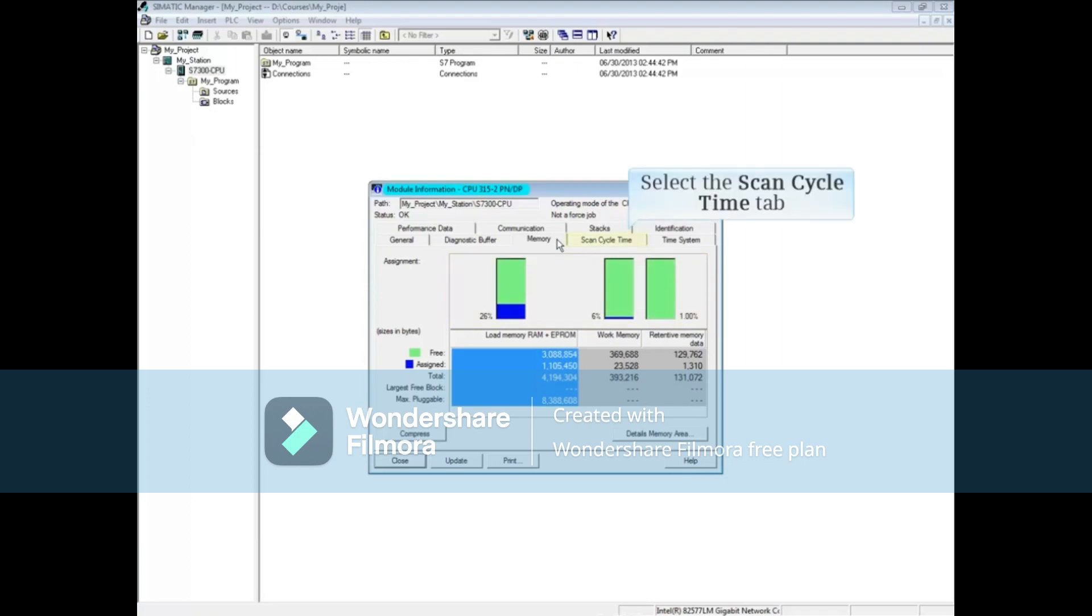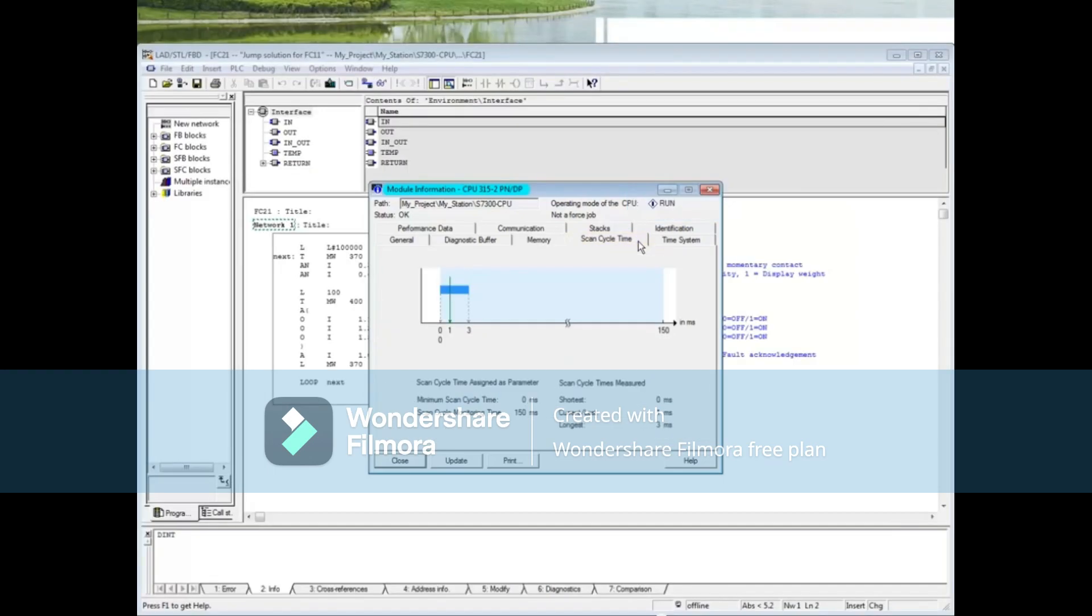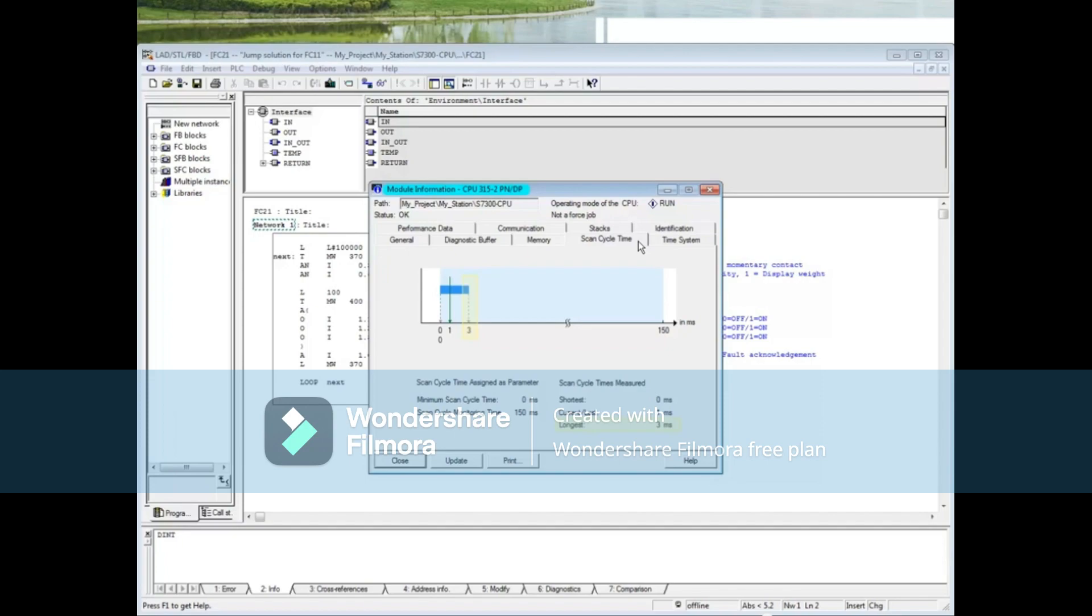Click on the Scan Cycle Time tab. This tab shows both graphically and in words the watchdog cycle time, which is 150 milliseconds, the longest scan cycle so far, which is 3 milliseconds, and the shortest scan cycle, which is 0 milliseconds.